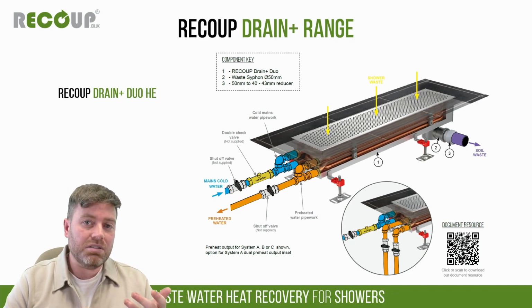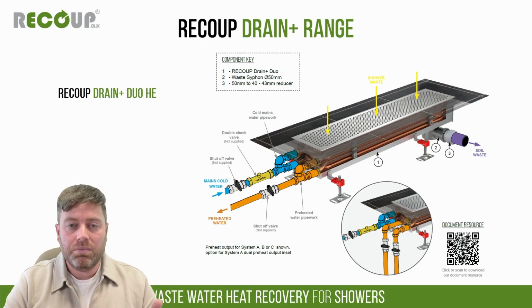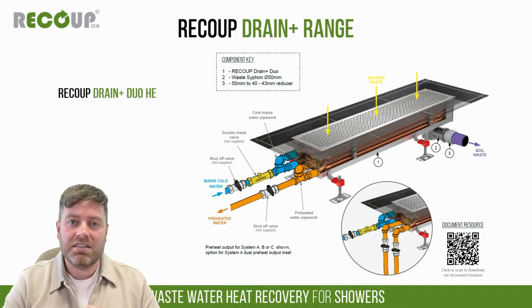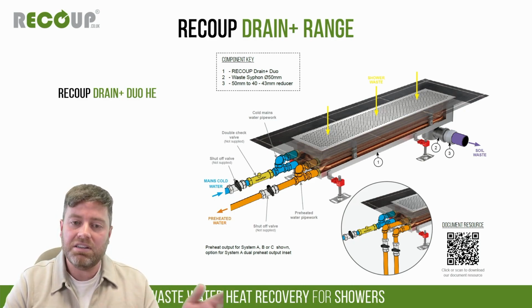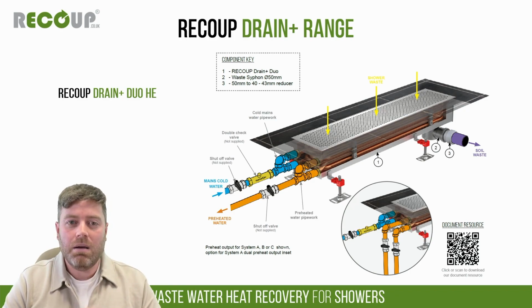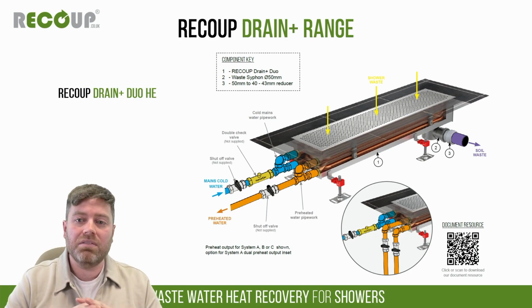Normally these are only used at end of life, possibly when isolating for pressure testing. They can be pressure tested up to 10 bar, so if you need to test higher than that, they need to be isolated. Generally it's just end of life use, so they don't need to be right next to the drain. We show them this way just for ease of demonstrating on an image, but often they're positioned somewhere accessible. The drain comes with levelling feet, so it can be levelled and positioned before being backfilled within the floor.